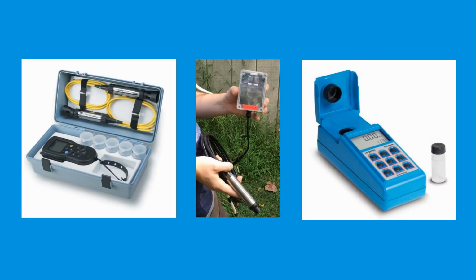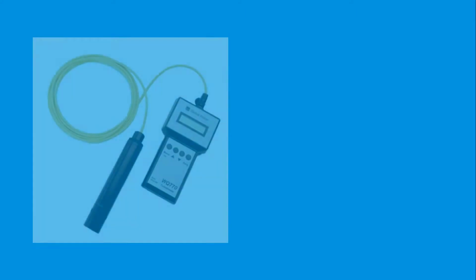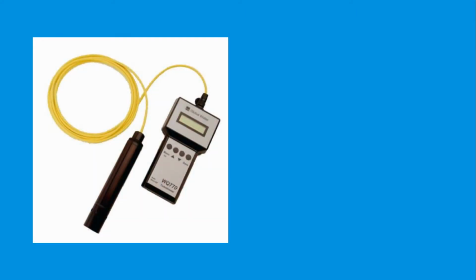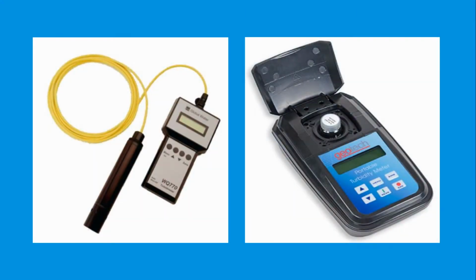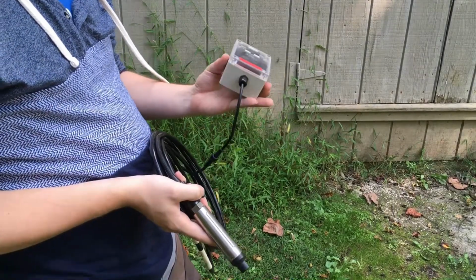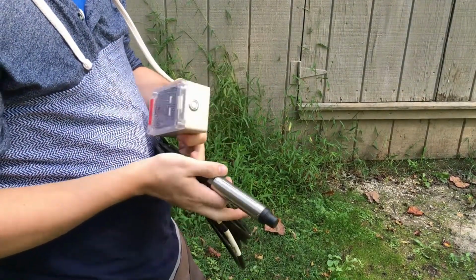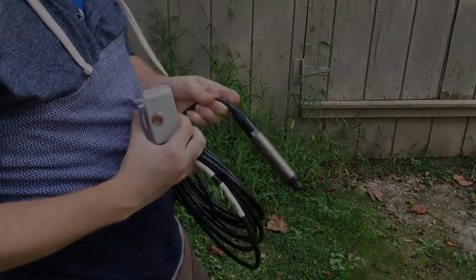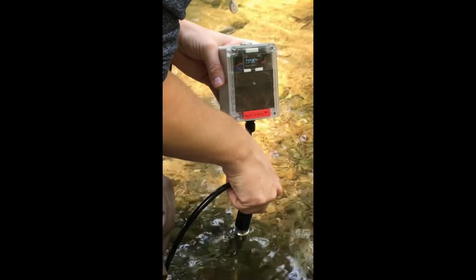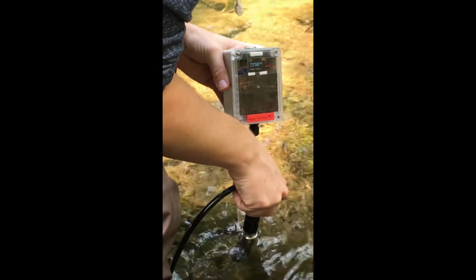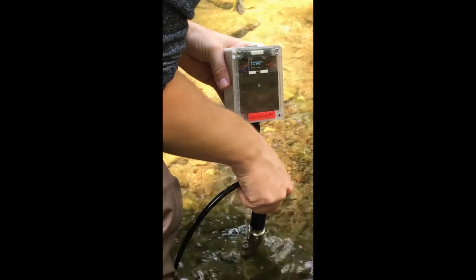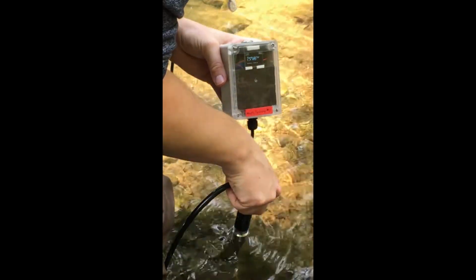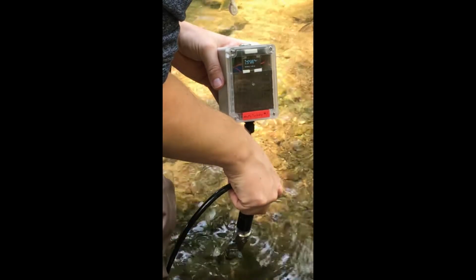Next is turbidity. There are a variety of instruments that can QC this parameter. You will take the calibrated instrument and dip the probe attachment into the stream, or you will take a small sample and attach it to the calibrated instrument to read. In Stroud's case, we use an in-house built instrument that attaches a Campbell Scientific Turbidity Probe to a mayfly board. The instrument is turned on by pressing a button. We then lower the probe into the water a few inches. We avoid getting too close to the stream bed and have the probe window facing away from the user.